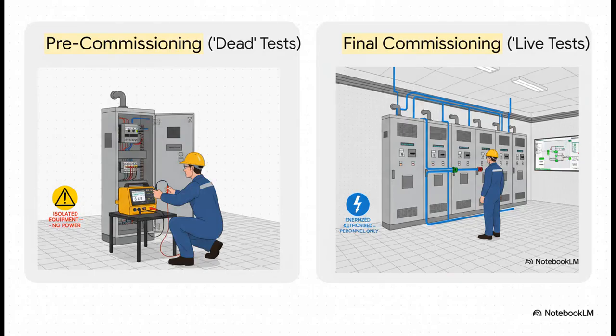And testing happens in two key stages. First is pre-commissioning. These are dead tests, meaning the main power is off. We're testing individual pieces of gear, checking insulation, making sure wires go to the right place, injecting signals into relays to see if they work. It's all about making sure the parts are good.